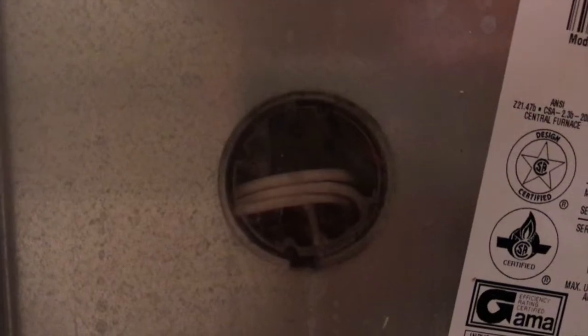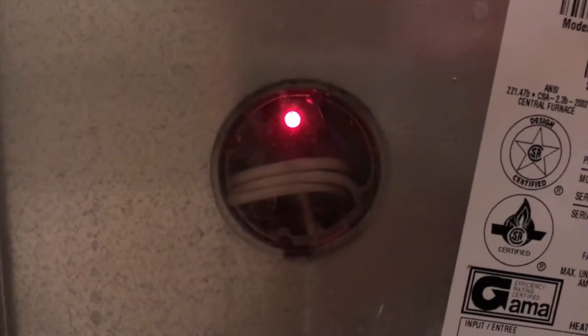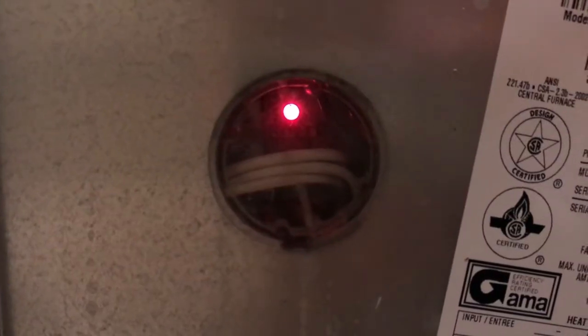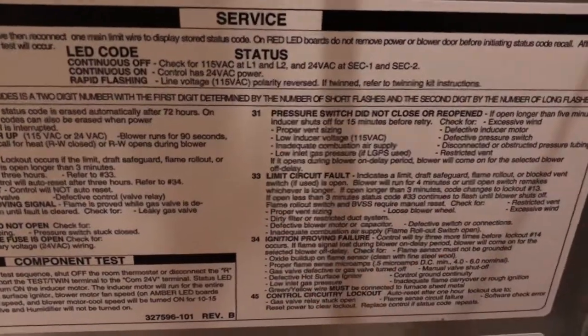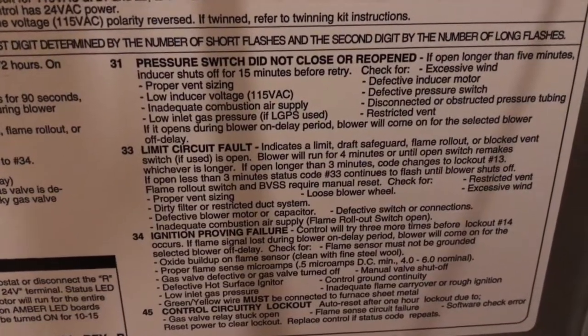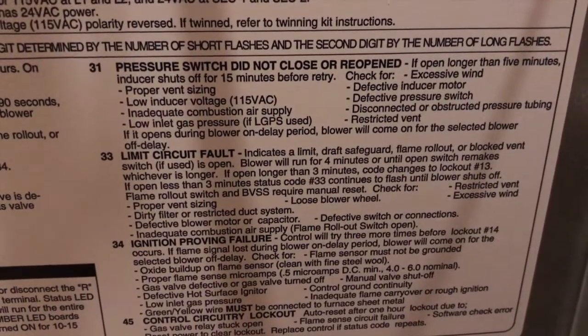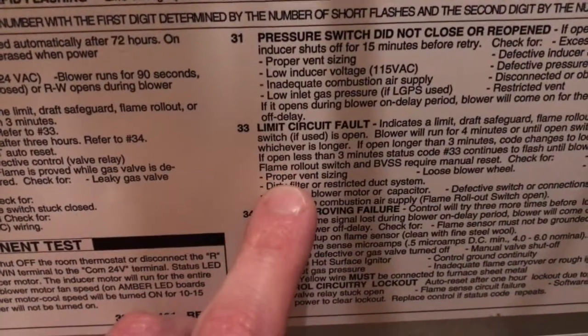So right now it's off — one, two, three, one, two, three. That is a 33 error code, and that is right here — that is a limit circuit fault. You need to read this entire thing: indicating limit, draft safeguard, flame rollout, or blocked vent switch if used is open.